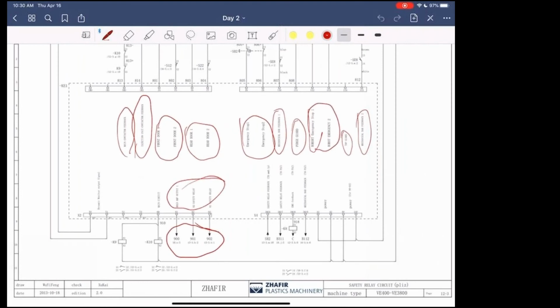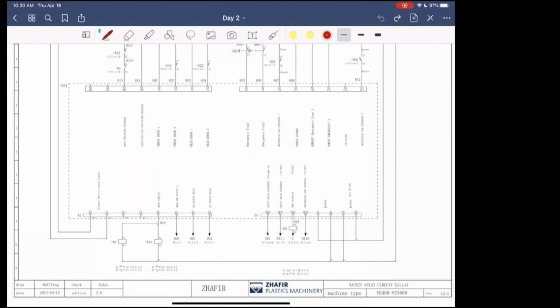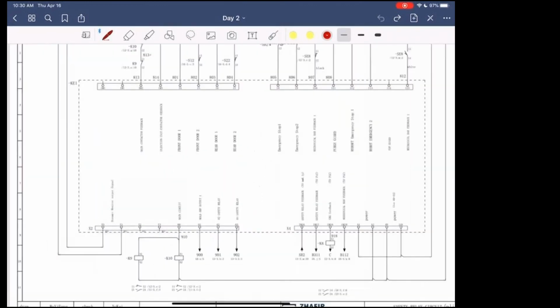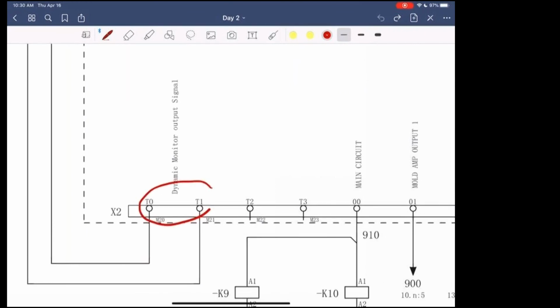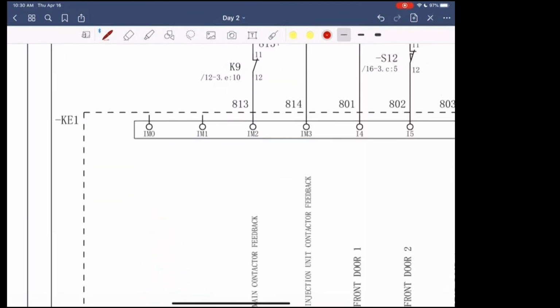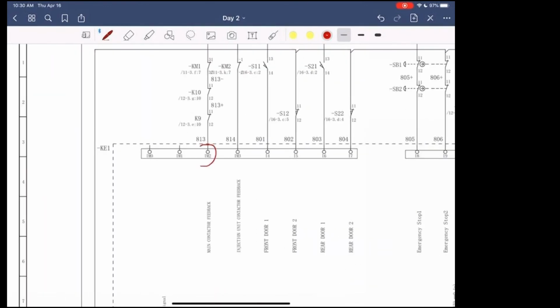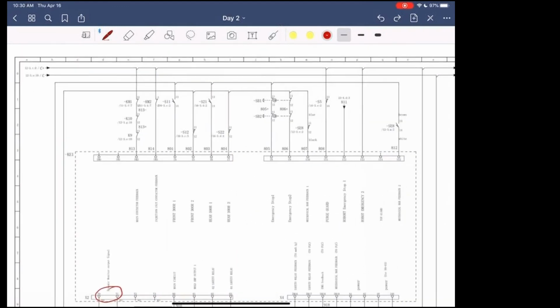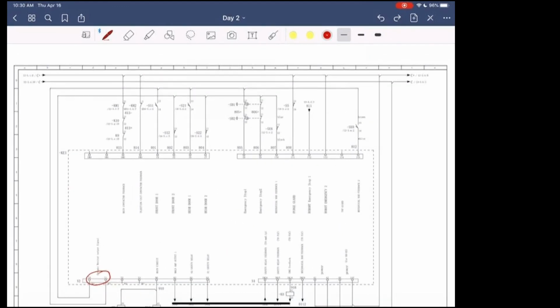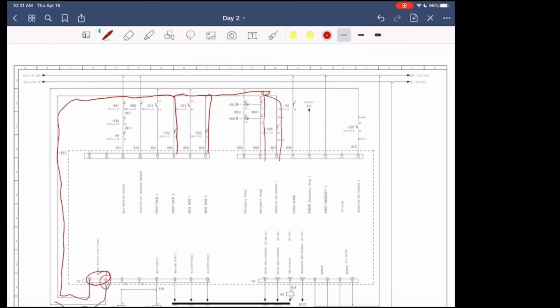All right, how does this guy work? This guy works off of this signal right here, this T0 and T1. You cannot just put 24 volts on any of these inputs up here. All of these are inputs. So this is input 2, 3, 4, 5, 6, 7, etc. They are going through the circuit through a pulse signal. This is T0 and T1. So it's not a straight 24 volts. So for example, T0 will go up here. It'll come down to this guy, come down to this one, come down to this one, and come down to here. The T1 on the dual channel circuits, it'll do every other one also.